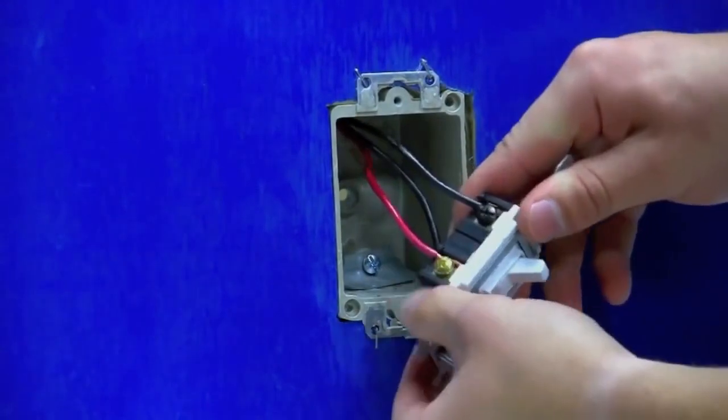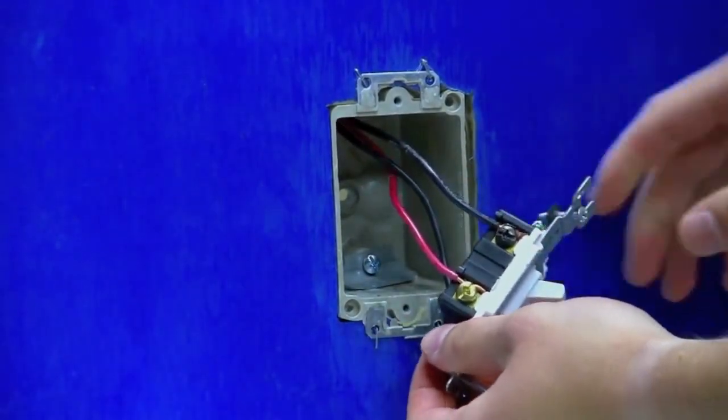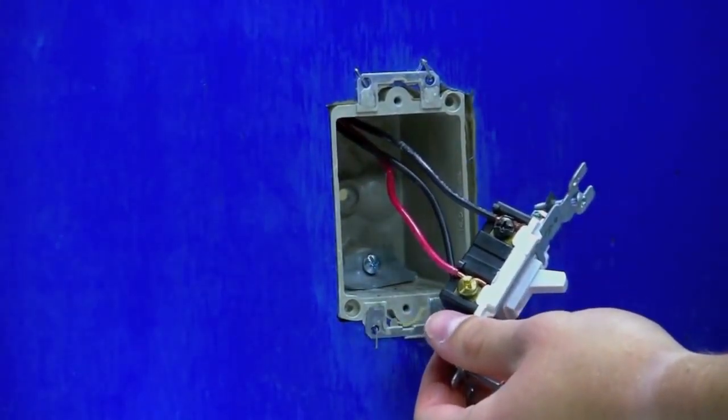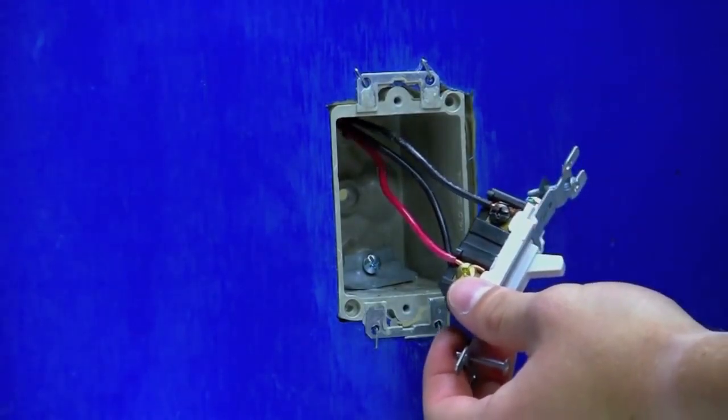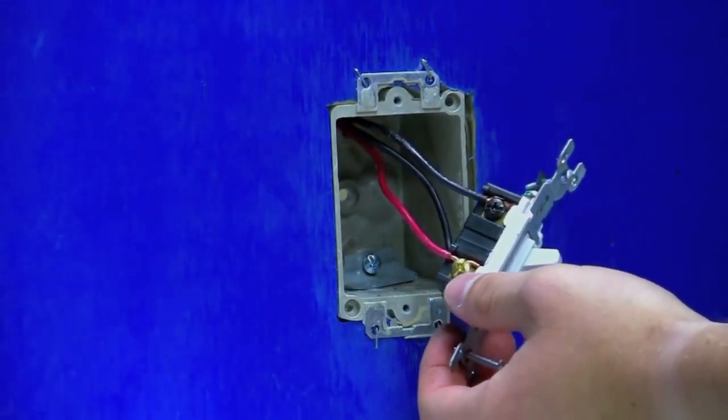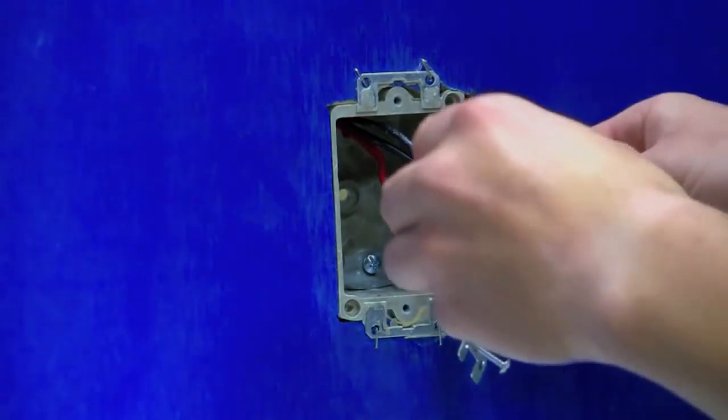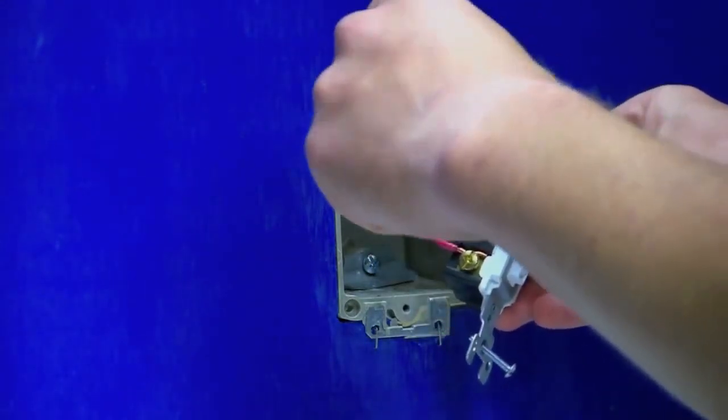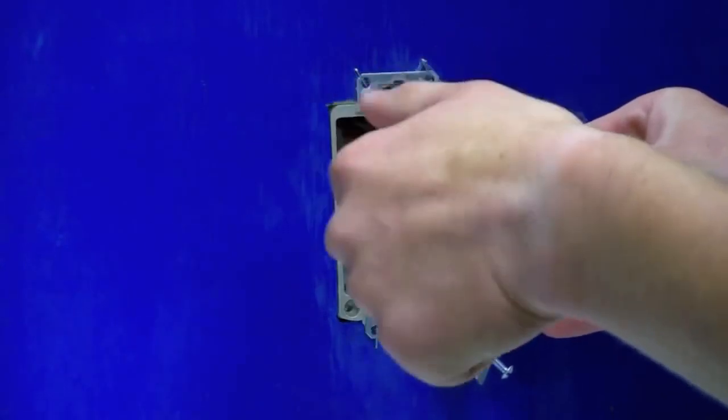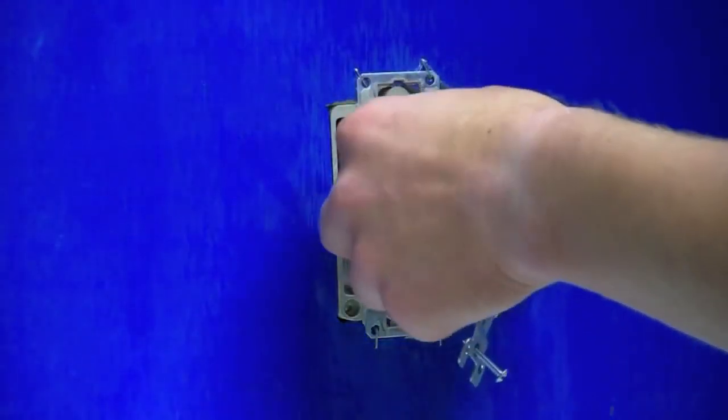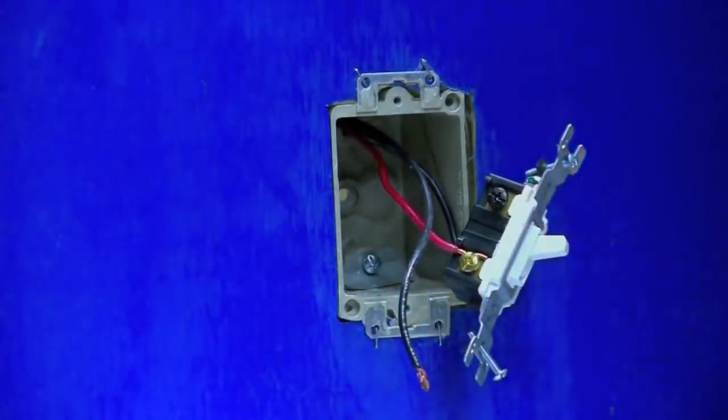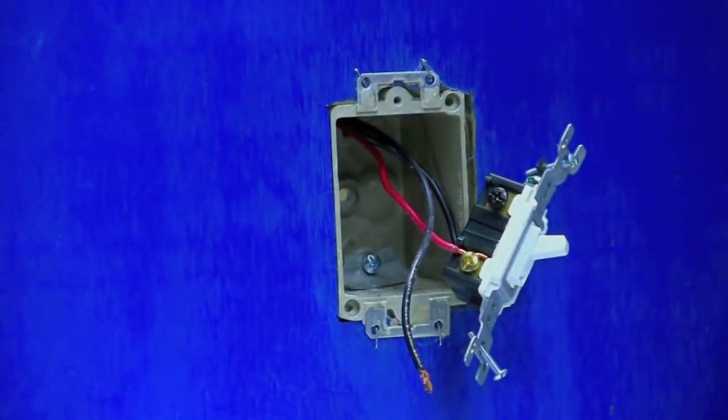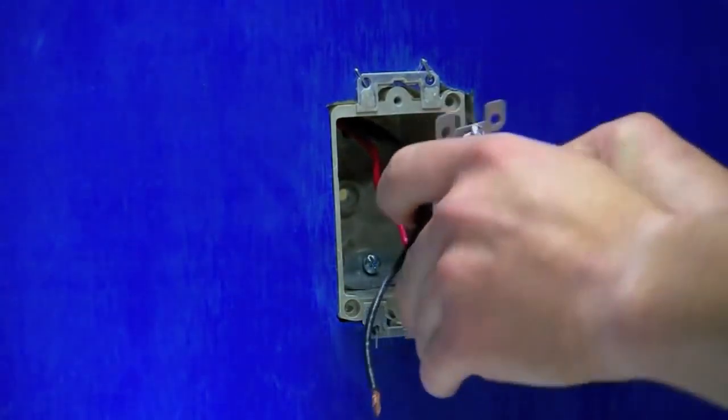Now that we've got the other three-way switch removed from the wall we need to again locate the common terminal and remove the wire from the common terminal. Again the common terminal on a three-way switch is the odd colored screw. Now that we have our common wire removed we need to remove the wire that we noted before that is connected to the blue wire from the switch.